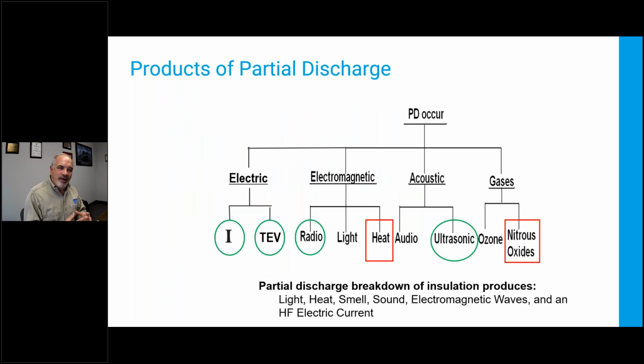So what happens when we have partial discharge? We have a variety of things happen, and some of them we care about, some of them we don't, and I'm going to go through this in random order. In the electromagnetic world, so we're talking radio waves, light waves, heat, things like that. So light, I can see it. It's a spark. It's visible. It's blue light. It's got some ultraviolet light to it, and that's how I can use a corona cam to find corona, or I can use a corona cam to find surface discharge, but I've got this light. Now, if I'm inside metal clad switchgear or I've got internal discharge, that light's not very useful to me.